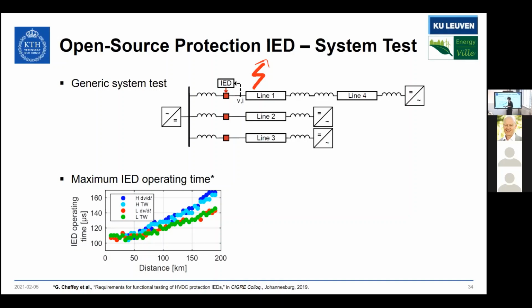So on the x-axis, you see distance in kilometers, and on the y-axis, you see the IED operating time in microseconds. And this IED operating time is measured from a 5% voltage deviation at the measurement point until trip output high at the IED output.